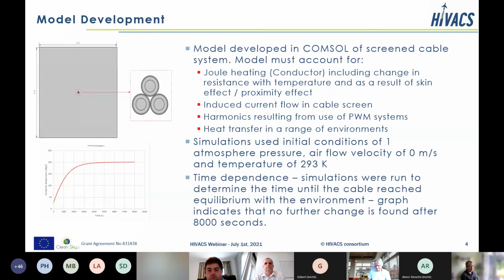The models we developed were in COMSOL. The model accounted for Joule heating, so the I squared R losses, which of course in turn had to model the change in resistance as a function of both temperature and skin effect and proximity effect. We looked at, of course, the induced current flow in the screen or the shield. And you'll see from the experimental data that Laurent will talk about, you'll see the importance of the current flow in the shield on the thermal capacity of the cable.